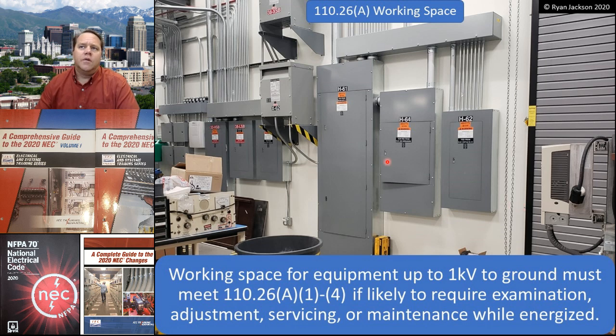Most people agree that panel boards, switchboards, switchgear, motor control centers, equipment like that needs to have full-blown working space. We can argue whether that's required for transformers or not, but really that is a matter of opinion. If you're the AHJ and you think transformers meet that criteria, then so be it. If you're an AHJ and you think they do not meet that criteria, that's okay too. Somebody has to make that determination.